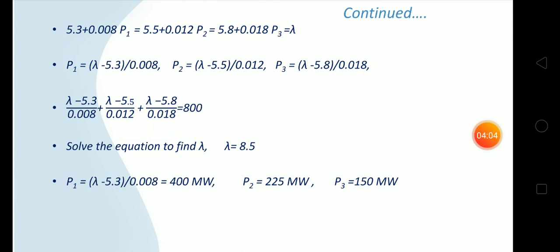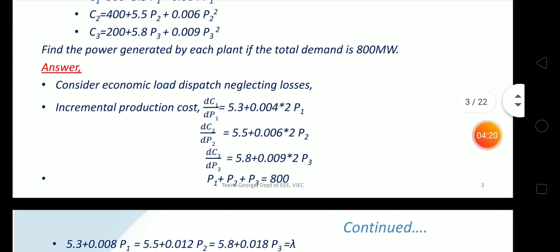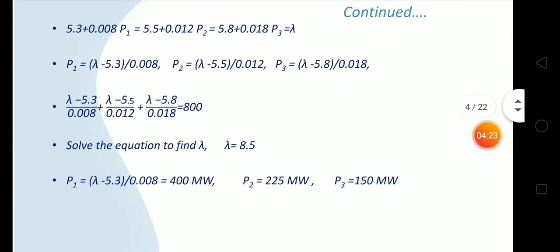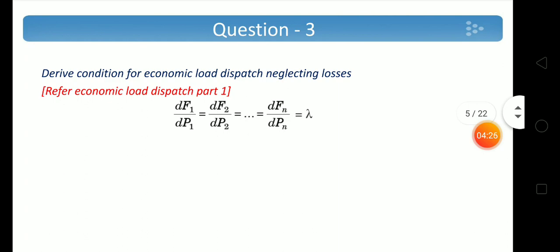P1 = (8.5 - 5.3)/0.008 = 400 MW. Similarly, P2 = 225 MW and P3 = 150 MW. This is the optimal generation of each plant to meet a load of 800 MW. Next question: Derive the condition for economic load dispatch neglecting the losses. The condition is dF1/dP1 = dF2/dP2 = ... = dFn/dPn = lambda; incremental fuel costs should be equal.